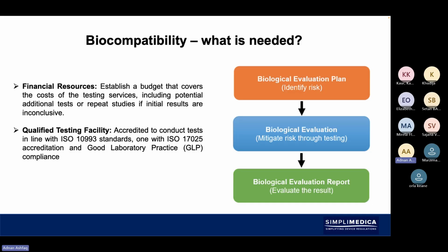So the methodology that you would have is to write a biological evaluation plan. This, again, no surprises, is identified by risk. So again, in your risk assessment, you would identify biological risks. You would then look at the biological evaluation that you might need to mitigate those risks through testing. So you might need to actually do in vitro testing or in vivo testing in animals, or even in human use, to try and justify that the materials that are being used are safe for use. And any testing that you're doing ideally should be done in laboratories which are accredited. So once you've got all of the results, you would then evaluate the results and write up a biological evaluation report.